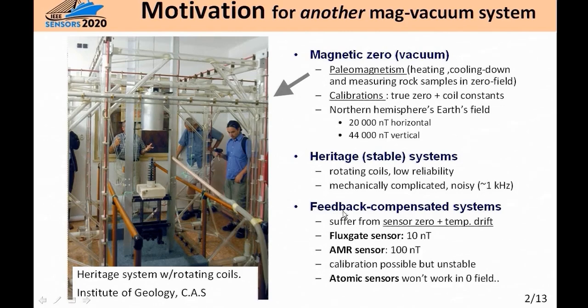There are also feedback compensated systems using, let's say, Fluxgate sensors or AMR sensors, the two vectorial sensors available, but these sensors suffer from offset and from temperature drift of the offset. It's possible to calibrate for them, for example in a magnetic shield, but these two parameters are really not stable in time and with temperature.